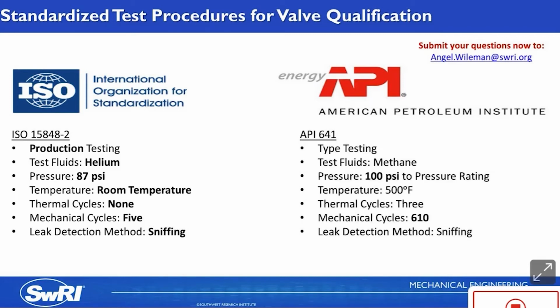API 641 is very similar to 624, but it's written for testing of quarter turn valves. The test pressure is defined based on the valve group in the standard, but it is a bit lower than 624 with a minimum of only 100 psi. And it also includes more mechanical cycles than 624 with 610.